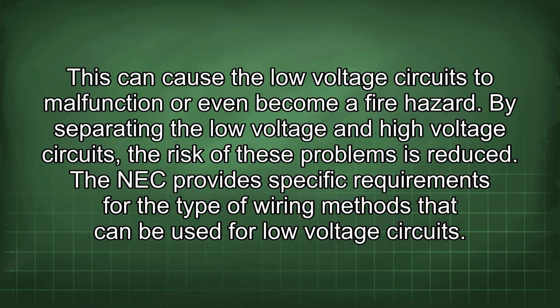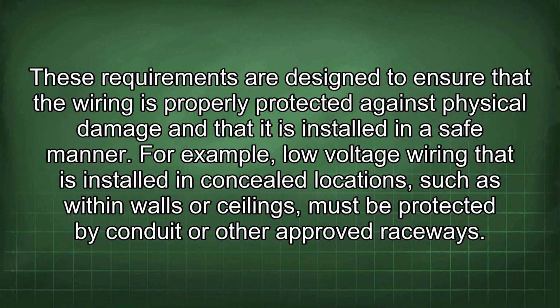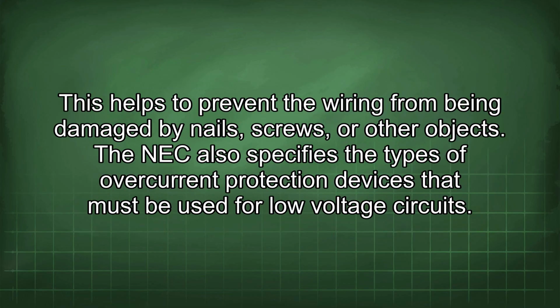The NEC provides specific requirements for the type of wiring methods that can be used for low-voltage circuits. These requirements are designed to ensure that the wiring is properly protected against physical damage and that it is installed in a safe manner. For example, low-voltage wiring that is installed in concealed locations, such as within walls or ceilings, must be protected by conduit or other approved raceways. This helps to prevent the wiring from being damaged by nails, screws, or other objects.